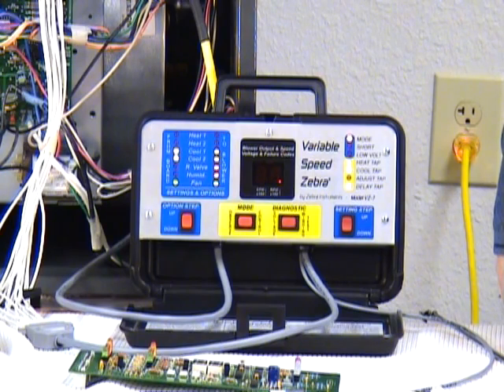Now, as time goes on, there are newer motors, one of which is a version 2.5, which is mostly used by Carrier, which uses a special communicating thermostat, which has software and sort of like a serial stream on your computer, like it goes to your modem. It uses a communications protocol from the thermostat to the motor that communicate back and forth. The variable speed zebra, nor any other tools that we know of at this time, can work with that motor. Most of those motors are in version 2.5. There's also a new protocol that just came out in early 2007 called the version 3.0 ECM motor, and currently there are no tools able to communicate with that motor.